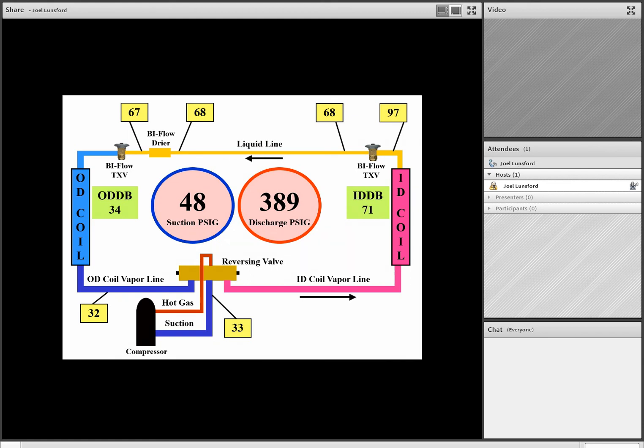Now here's the service call. The homeowner said it worked fine in the cooling mode. But in the heating mode of operation, we see the suction pressure drop down significantly, and we're supposed to be flowing freely on that indoor TXV, but we see that the check valve circuit is restricted, and we have a big temperature drop across that bi-flow TXV on the indoor coil that should be flowing freely. So in this example here, we have an indoor TXV restricted check valve circuit.